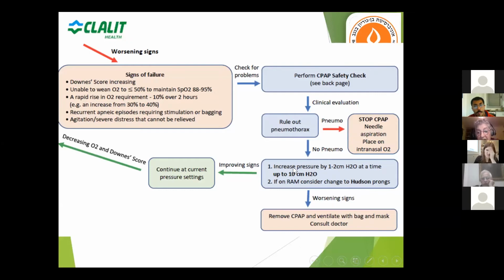If there is no pneumothorax, then you increase the pressure by 1 or 2 centimeters of water. And remember that you can increase up to 10 centimeters of water in order to reach better saturation in a baby. If the RAM cannula is considered inappropriate and you have other cannulas like the Hudson, you might consider changing to this. Some hospitals would have the Hudson prongs, but most of the hospitals use the ones that we are using in our unit. And if this is not helping, then you start ambu bagging. If the baby improves, then you go back to the other green part of this algorithm.